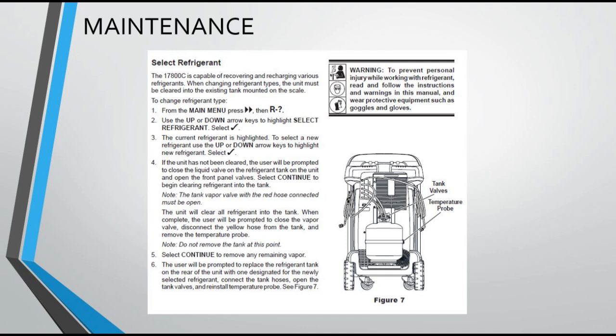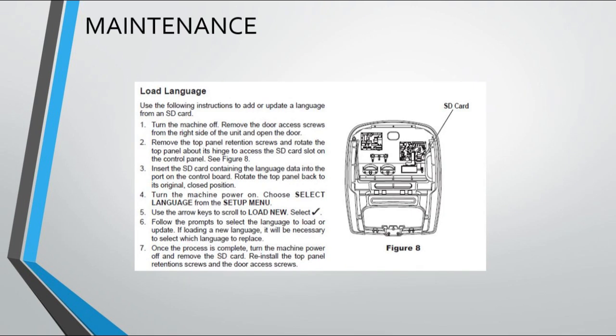6. The user will be prompted to replace the refrigerant tank on the rear of the unit with one designated for the newly selected refrigerant, connect the tank hoses, open the tank valves, and reinstall the temperature probe. See Figure 7. Load language. Use the following instructions to add or update a language from an SD card.